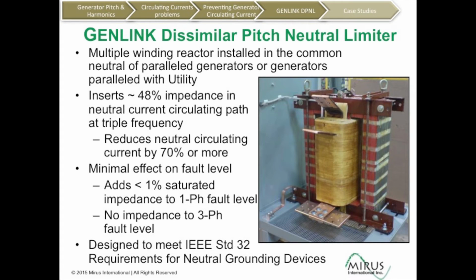So the GenLink DPNL is a multiple winding reactor that's installed in the common neutral of parallel generators or generators that are paralleled with the utility. It inserts approximately 48% impedance in the neutral circulating path at the triple frequency. So it's a very high impedance, and that's why it's so effective in blocking it. And this can reduce neutral circulating currents by 70% or more, often eliminating it altogether.